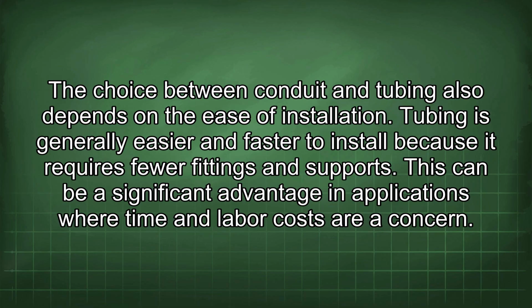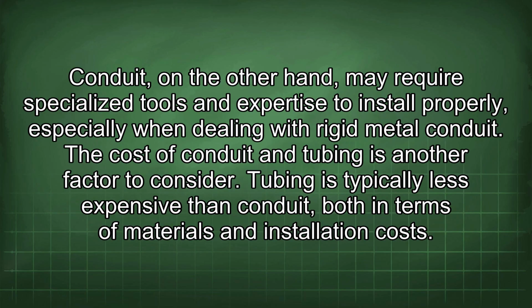The choice between conduit and tubing also depends on the ease of installation. Tubing is generally easier and faster to install because it requires fewer fittings and supports. This can be a significant advantage in applications where time and labor costs are a concern. Conduit, on the other hand, may require specialized tools and expertise to install properly, especially when dealing with rigid metal conduit.